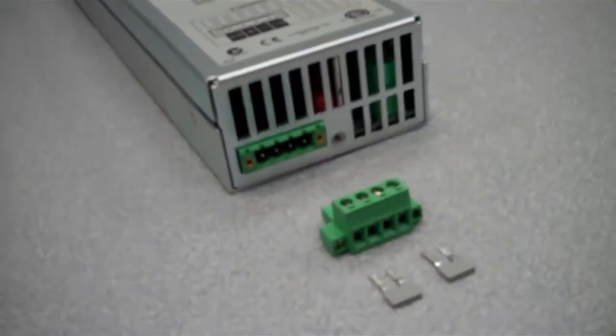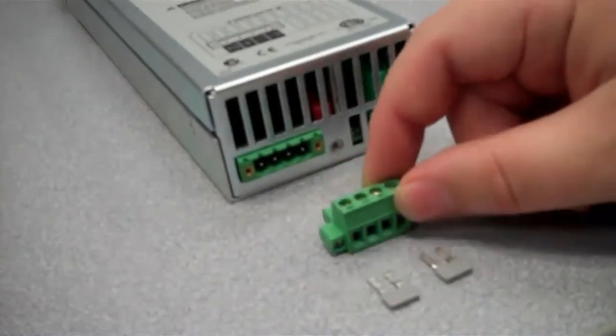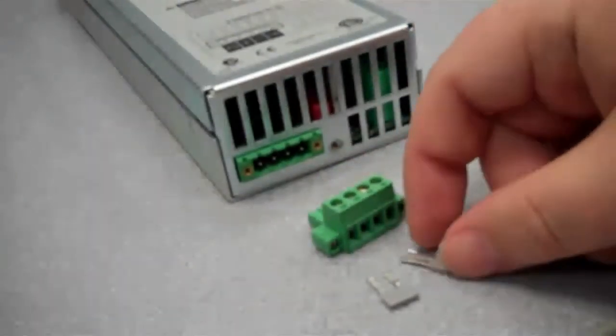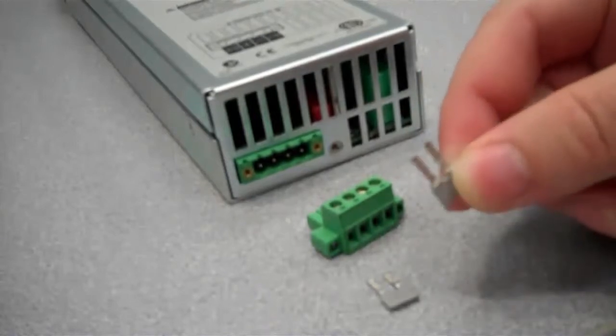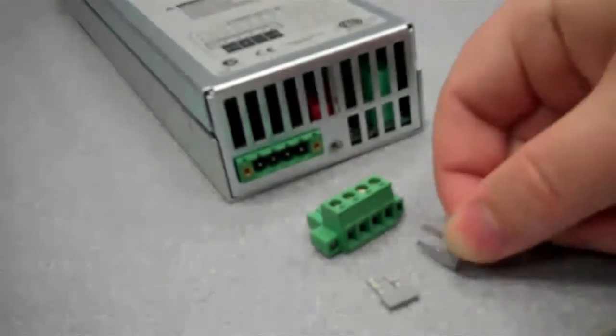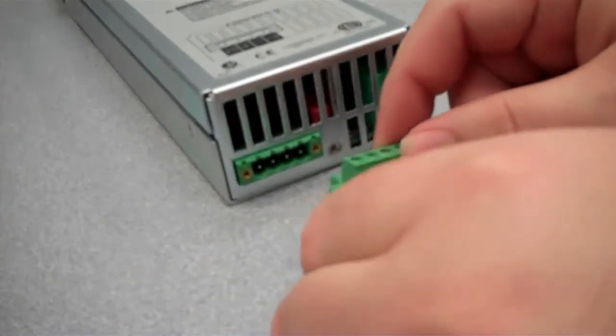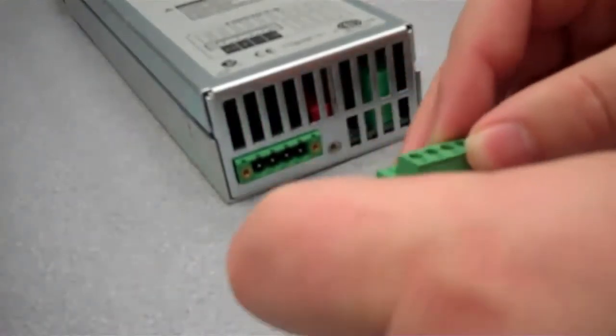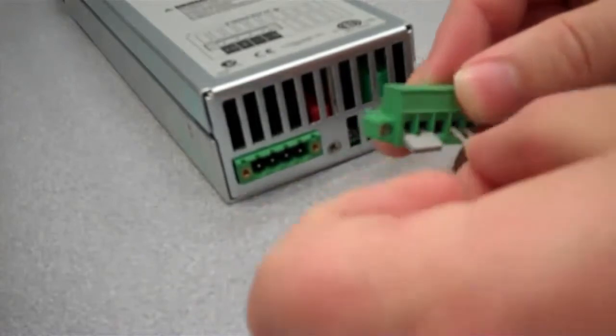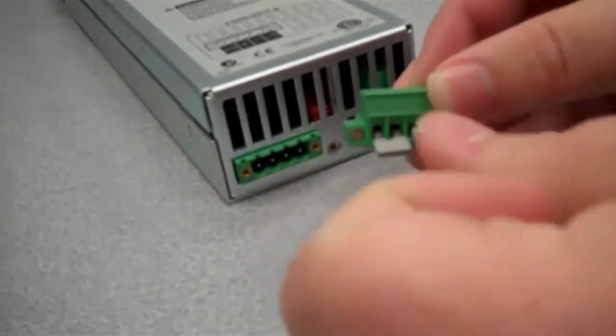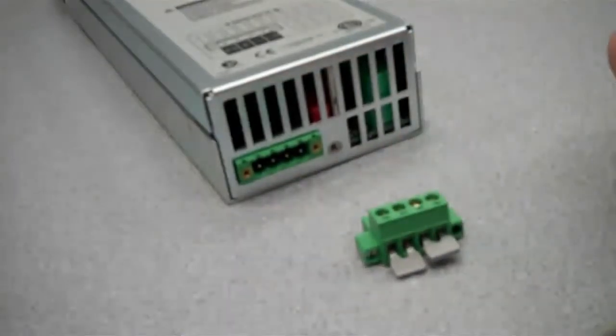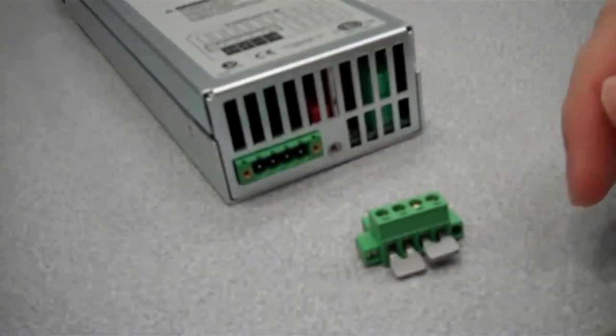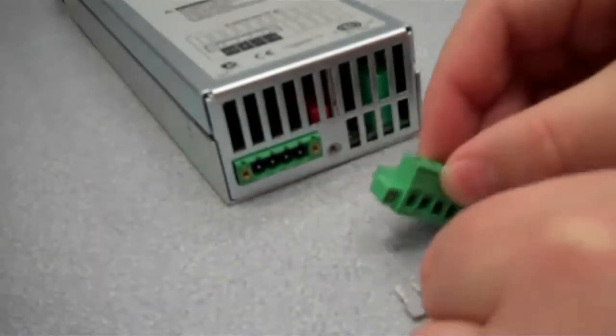There are two parts here. This green plug is the output connector and these little gray and metal pieces are the sense jumpers. When you want local sense on the power supply, you basically just take the jumper, put it inside like so, and then screw it down. Once you screw it down, you'll short the sense to the output to put it in local sense.